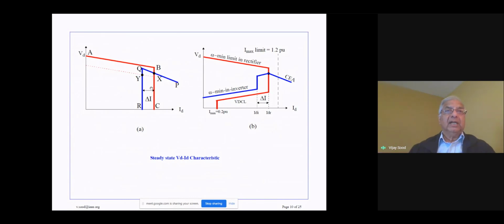So normally what happens is now the DC transmission system will be operating at this point X. Sometimes what happens if the AC voltage at the rectifier changes, if it drops down by a certain value, then this characteristic over here, AB, can shift downwards. And if that happens, then the operating point will move from X to Y.